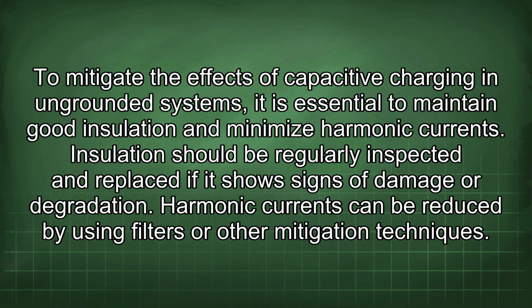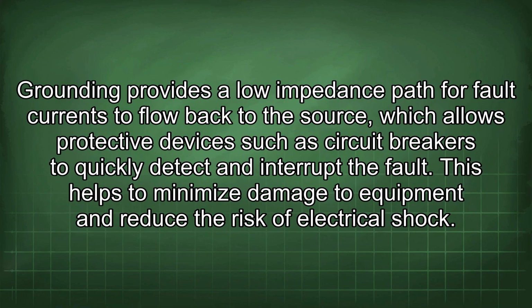To mitigate the effects of capacitive charging in ungrounded systems, it is essential to maintain good insulation and minimize harmonic currents. Insulation should be regularly inspected and replaced if it shows signs of damage or degradation. Harmonic currents can be reduced by using filters or other mitigation techniques. Grounding provides a low impedance path for fault currents to flow back to the source, which allows protective devices such as circuit breakers to quickly detect and interrupt the fault. This helps to minimize damage to equipment and reduce the risk of electrical shock.